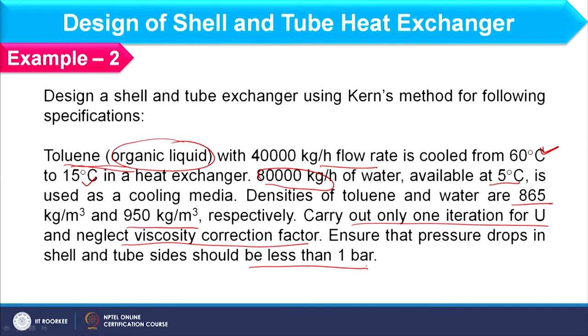Here we have the combination of toluene and water, whereas in the previous lecture we had benzene and water. The problem is similar to the previous one; however, some variations will be required, which is why I have taken this example to illustrate the design. First of all, we have to find out the heat duty, and for that we have to find the specific heat.